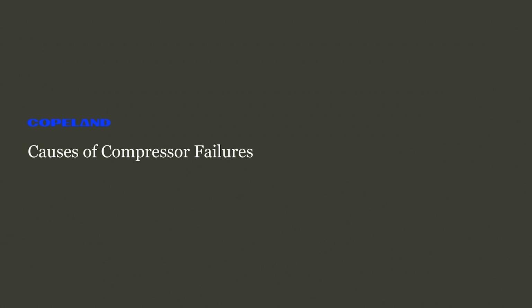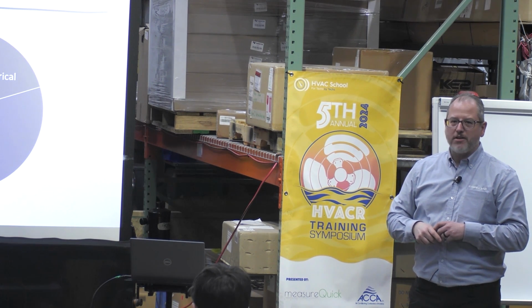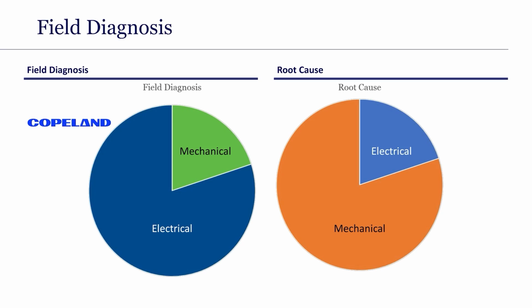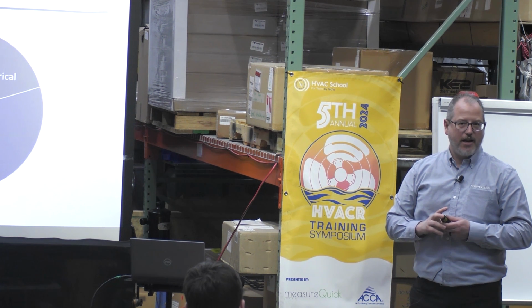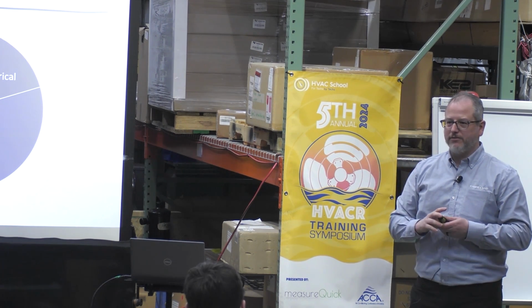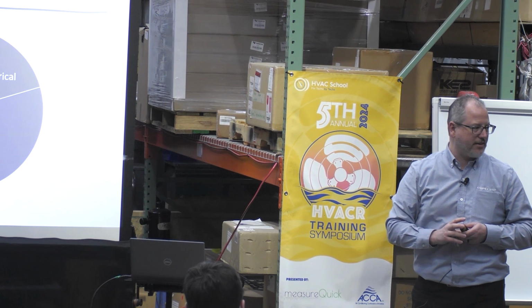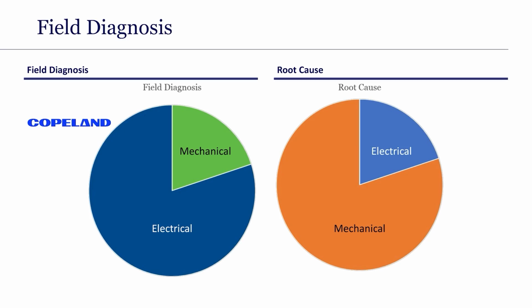All right, getting into compressor failures. When we get compressors back under warranty, 80% of them, on the tag, will say an electrical problem. But when we tear them apart, 80% of it is actually a mechanical failure that caused the electrical failure. The people that take apart our compressors are really good at what they do, and they can do chemical breakdowns of everything and find out what's inside that system. So the root cause is what we're concerned about. When you take apart a compressor, you can actually see what's going on in that system. What do I need to fix, right?